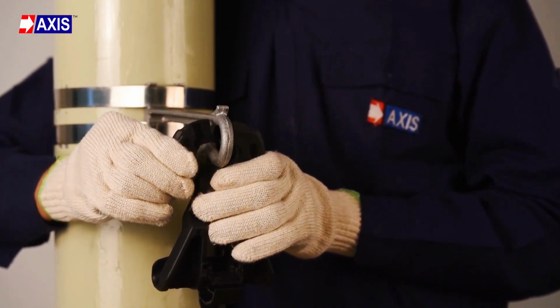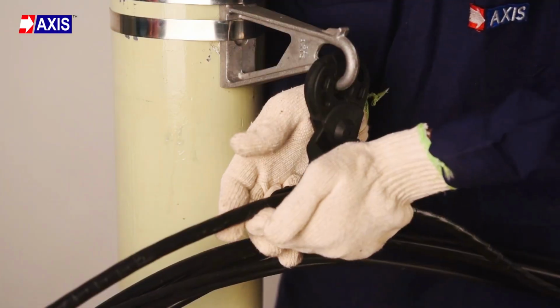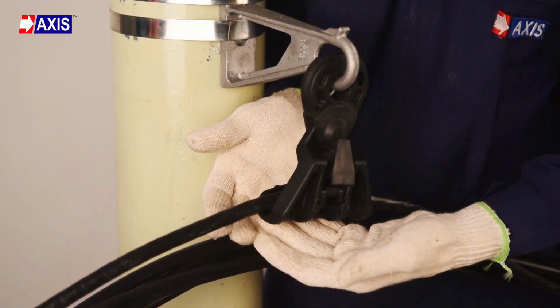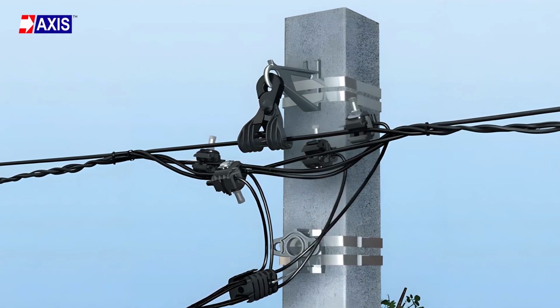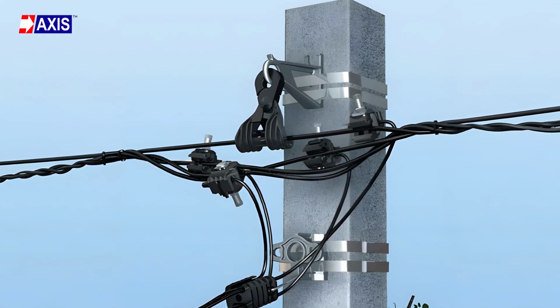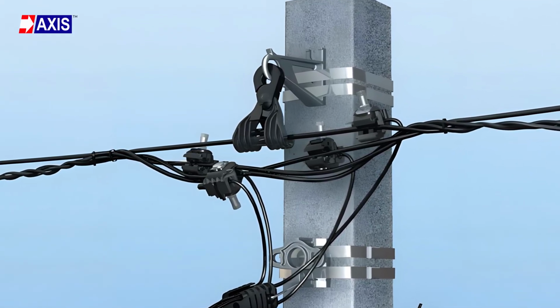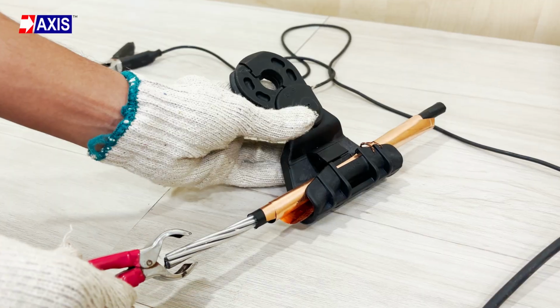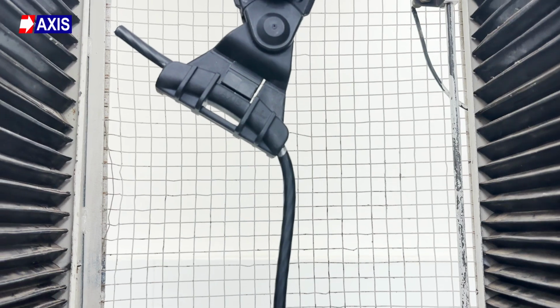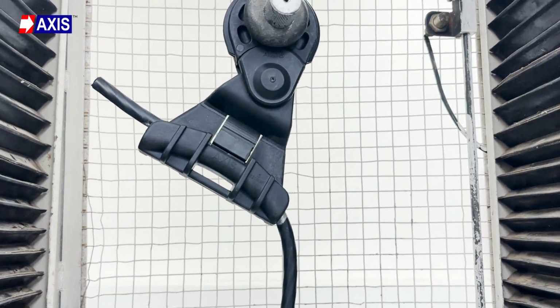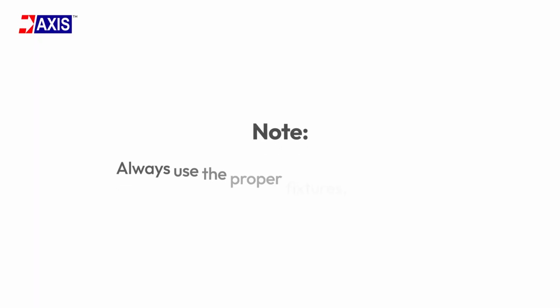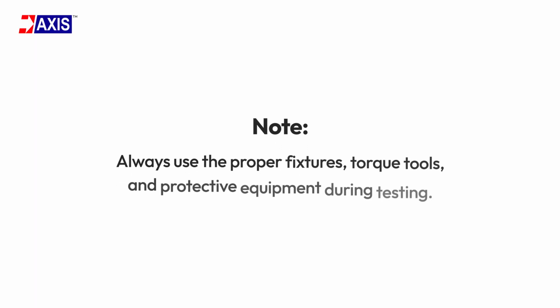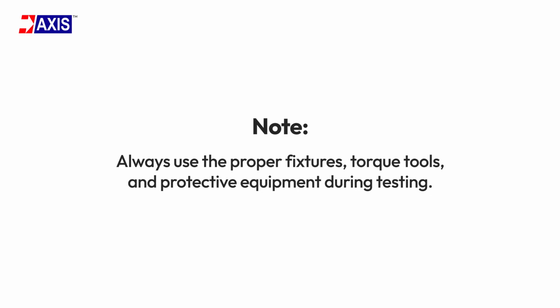Suspension clamps support and hold the messenger cable in an aerial bundle cable system. They carry electrical and mechanical loads under harsh outdoor conditions. These tests confirm that the clamp provides proper insulation, mechanical strength, and grip during real service conditions. Note: always use the proper fixtures, torque tools, and protective equipment during testing.